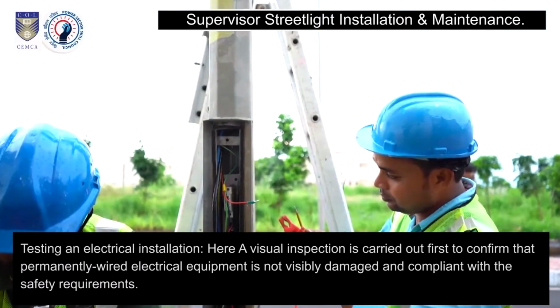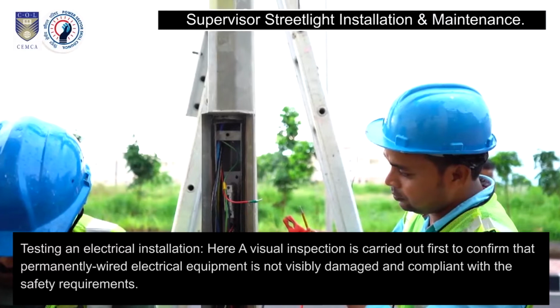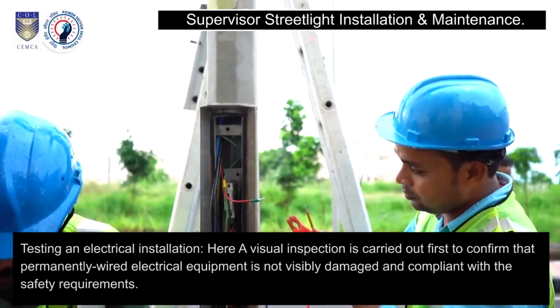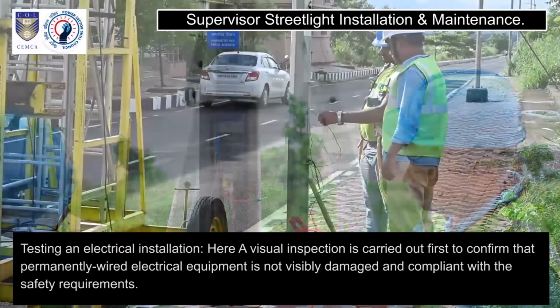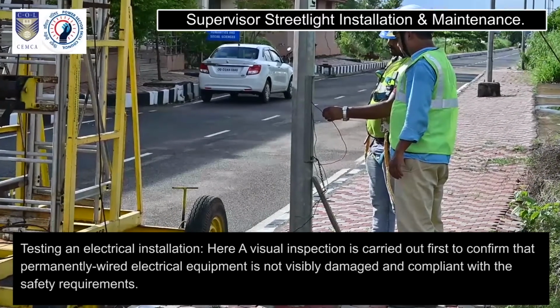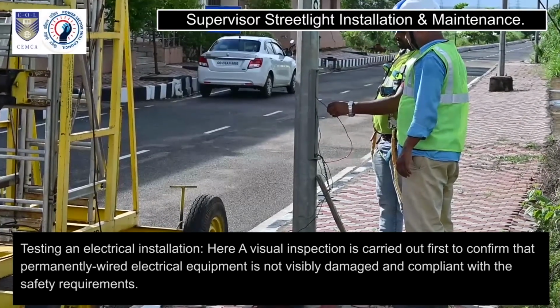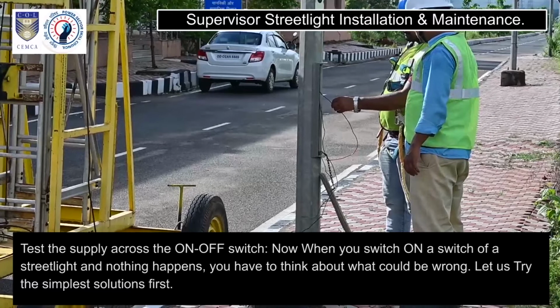Testing an electrical installation. Here a visual inspection is carried out first to confirm that permanently wired electrical equipment is not visibly damaged and compliant with the safety requirements. Test the supply across the on-off switch.